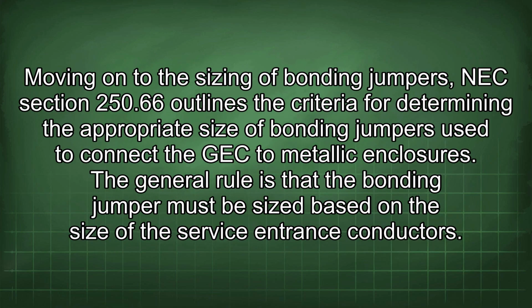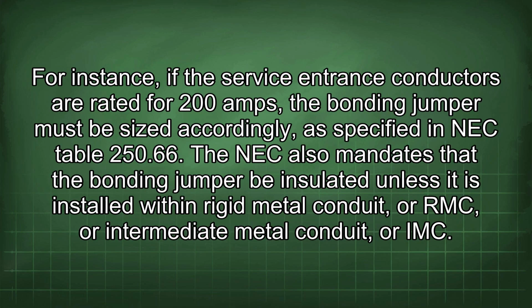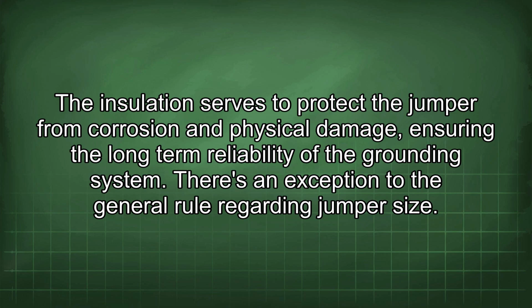Moving on to the sizing of bonding jumpers, NEC section 250.66 outlines the criteria for determining the appropriate size of bonding jumpers used to connect the GEC to metallic enclosures. The general rule is that the bonding jumper must be sized based on the size of the service entrance conductors. For instance, if the service entrance conductors are rated for 200 amps, the bonding jumper must be sized accordingly, as specified in NEC table 250.66. The NEC also mandates that the bonding jumper be insulated unless it is installed within rigid metal conduit, or RMC, or intermediate metal conduit, or IMC. The insulation serves to protect the jumper from corrosion and physical damage, ensuring the long-term reliability of the grounding system.